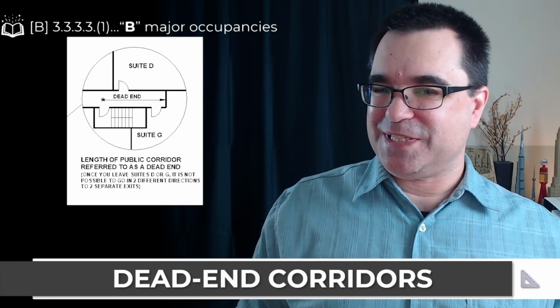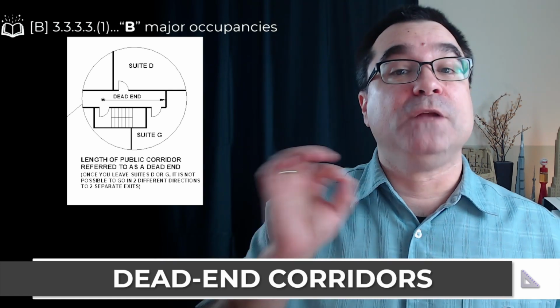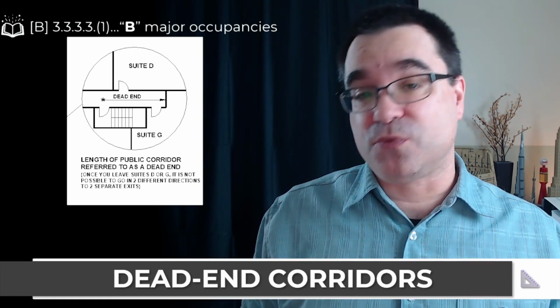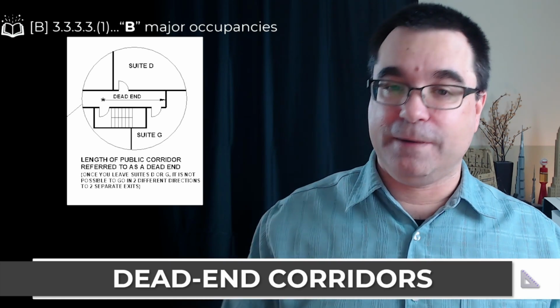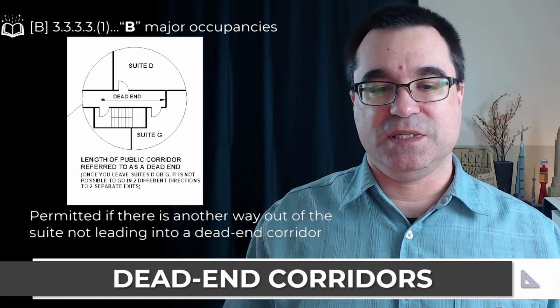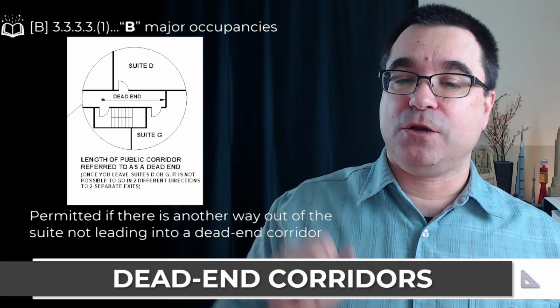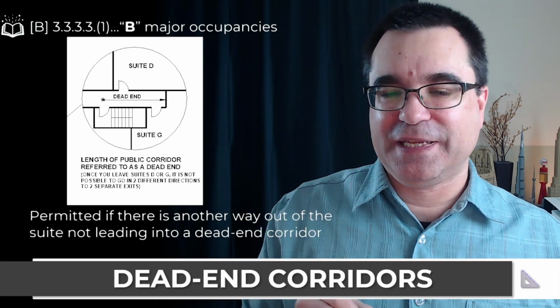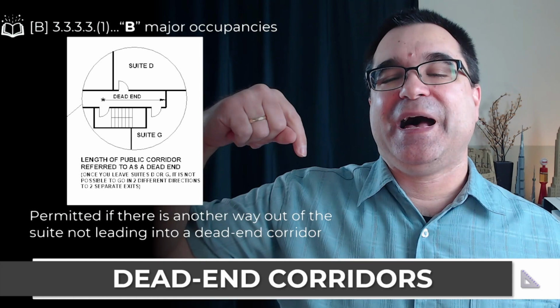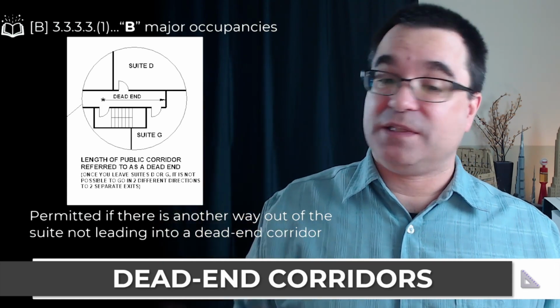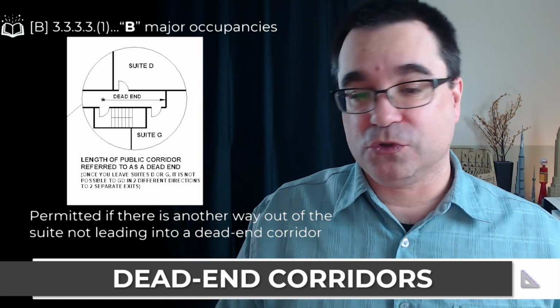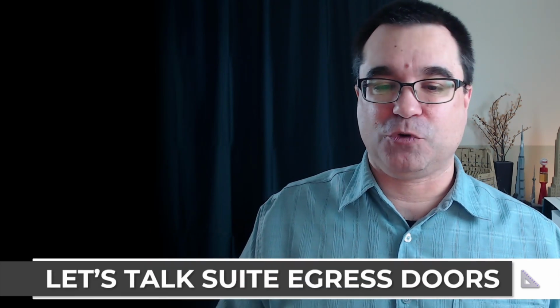B major occupancies, remember those? Under sentence 3.3.3.3(1), B major occupancies allow dead-end corridors if and only if there is another way out of that suite that does not lead into the public corridor and the dead-end corridor, okay?